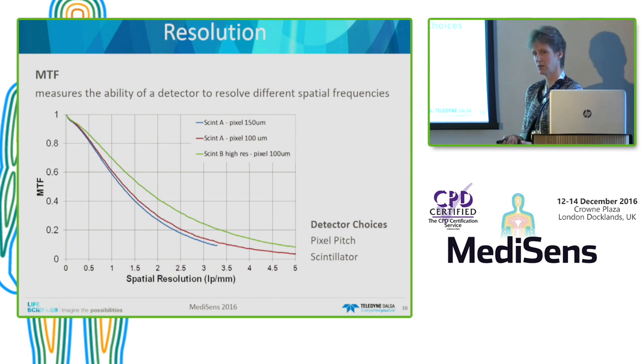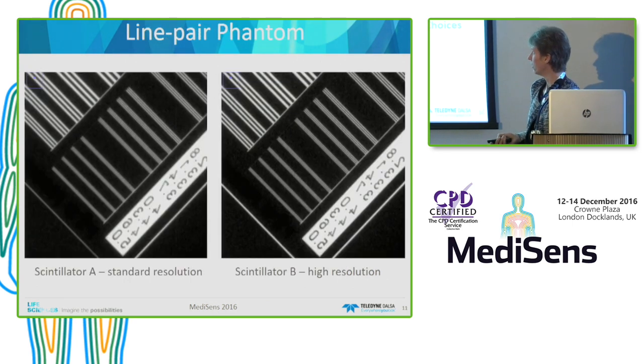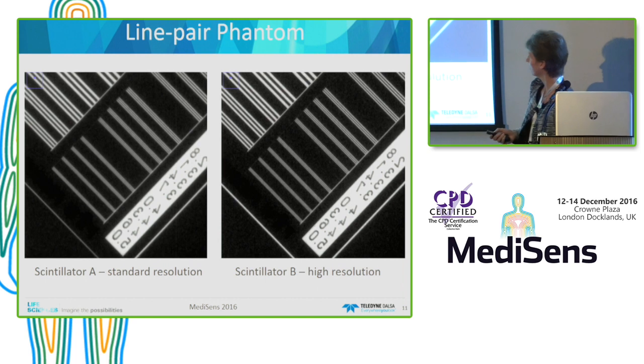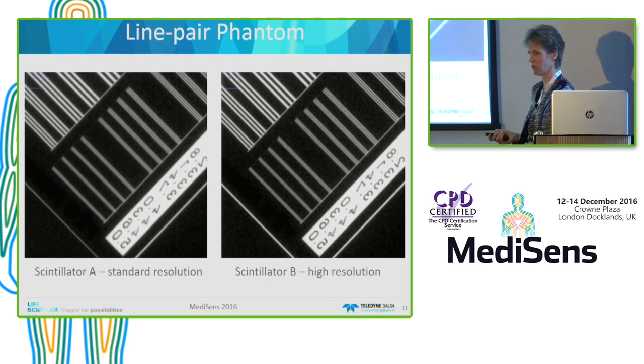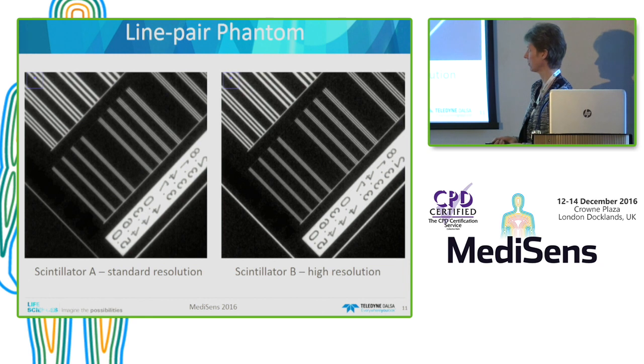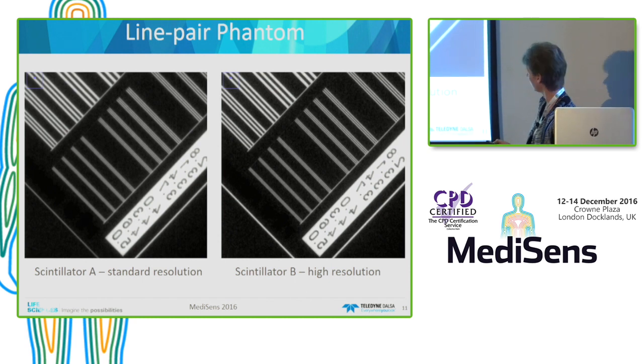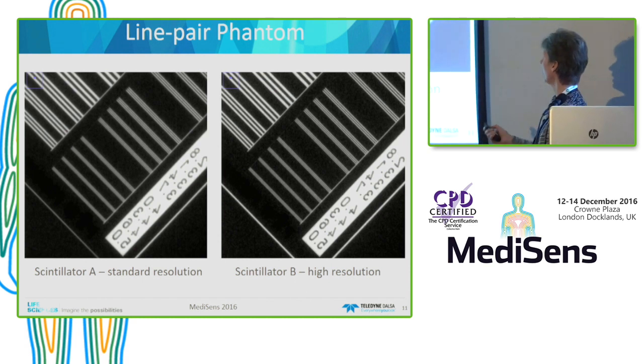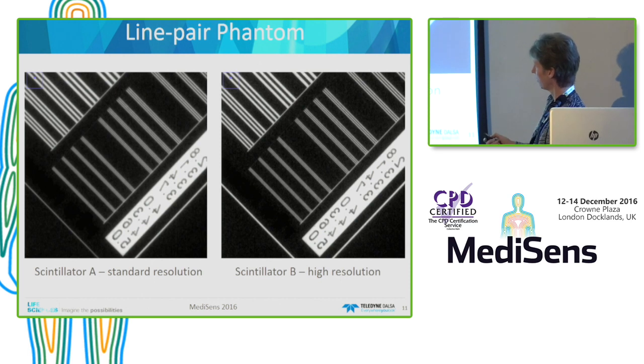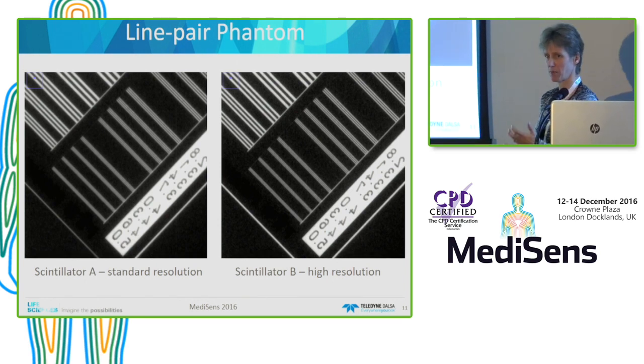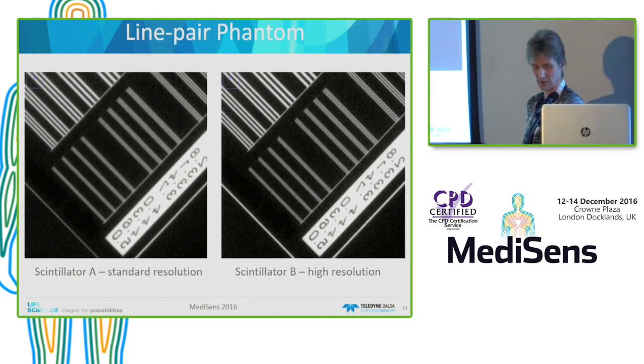So when designing a detector, you have to choose the pixel size and the scintillator material. To show the effect of MTF performance on a resolution image, this is a line pair phantom image for the high resolution detector and the standard detector under identical dose conditions. You can clearly see that the high resolution detector images the lines much more sharply — 5 line pairs per millimeter is visible — while the standard resolution detector doesn't have sharp transitions on the lines, and 5 line pairs per millimeter is no longer visible.